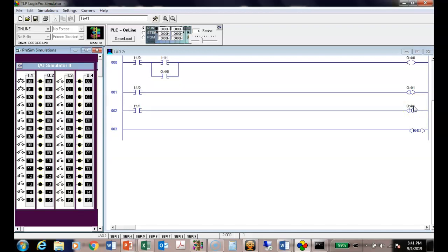On this guy, guys, you'll always use these in pairs, right? You understand? So once you latch, you do what sooner or later? Unlatch. So watch this. I'm gonna close 0, and notice that output turned on. How long is it gonna stay on? Until we unlatch it, right? So I'm gonna pulse this. I'm gonna make this circuit true. So this is simulating that relay that I'm passing around right now. And it basically is a lot simpler to use than this guy right here.